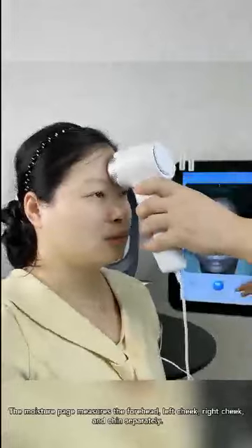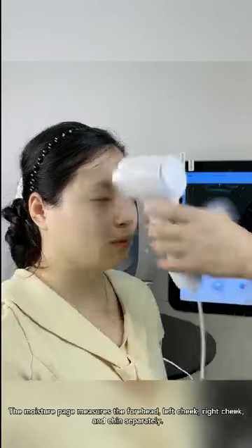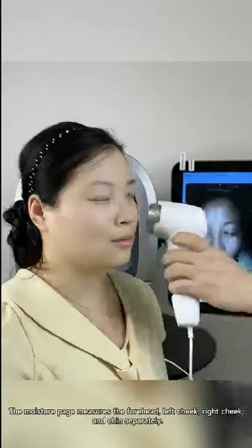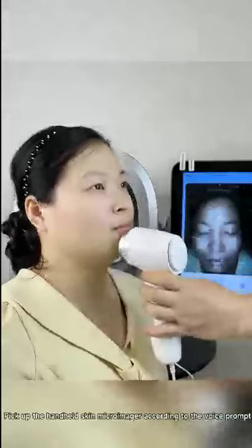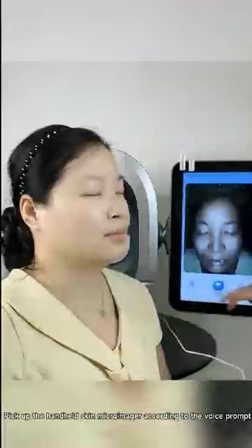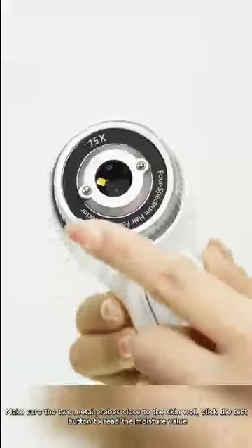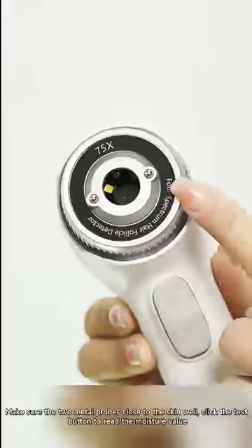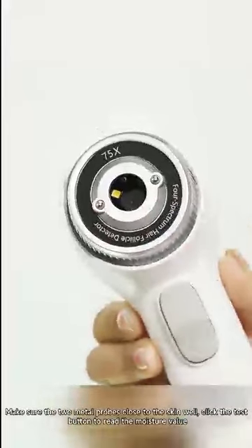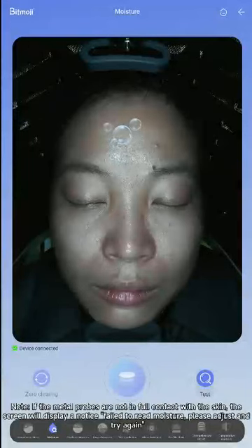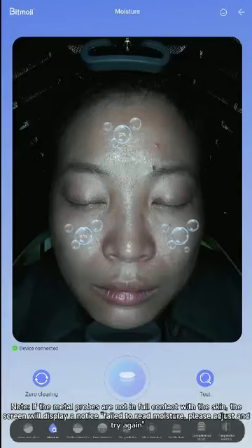Skin Moisture Content. The moisture page measures the forehead, left cheek, right cheek, and chin separately. Pick up the handheld skin microimager according to the voice prompt. Make sure the 2 metal probes close to the skin well. Click the Test button to read the moisture value. Note, if the metal probes are not in full contact with the skin, the screen will display a notice failed to read moisture.